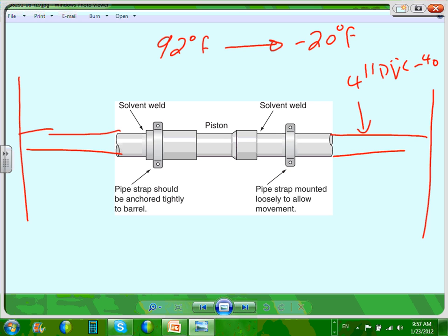If you are a contractor, this is a big deal. When you have runs of PVC conduit, they have a little piece called an expansion fitting. You have to put expansion fittings in every 50 to 100 feet of run, and it's size based. The expansion fitting is sized based on the temperature variation in the area. Temperature variation in Arizona will be completely different than in Minnesota. So be aware of that expansion fitting.